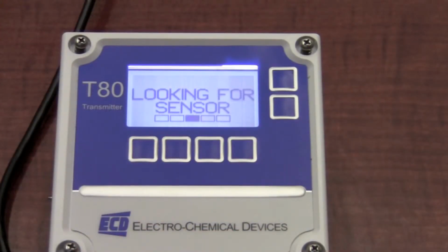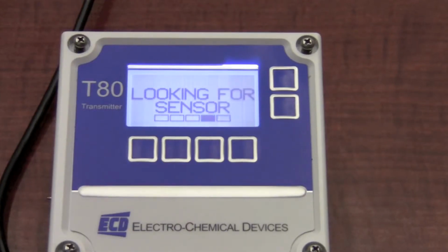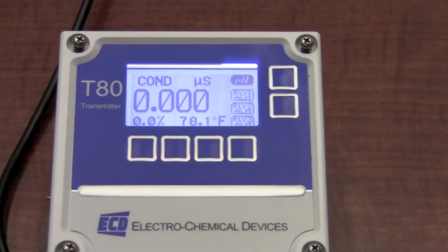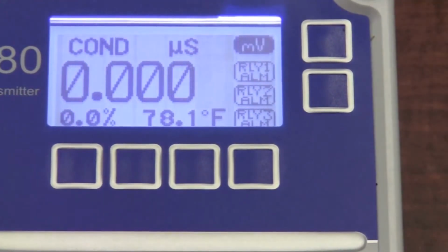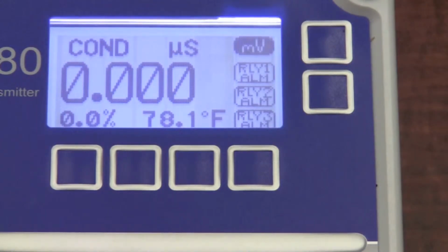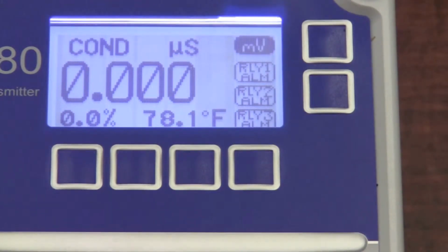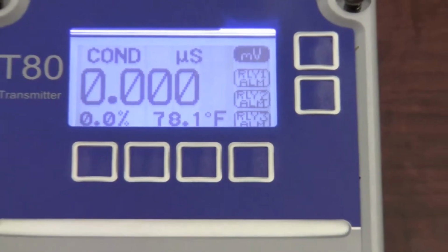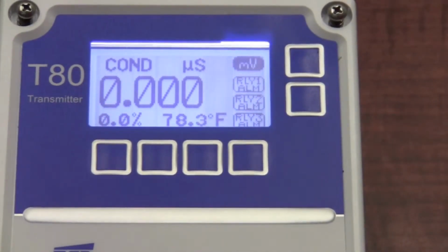Upon power up of the T80 intelligent transmitter, it's looking for a sensor. Once a sensor is connected, it interrogates the sensor for the type and span of measurement. I've just connected a conductivity sensor. And you see on the display, I show the type of measurement, conductivity. I show it in microsiemens. I show the percentage of output and the temperature. On the right-hand side, I show a status of the internal relays.